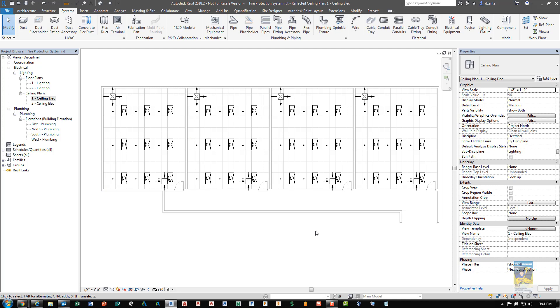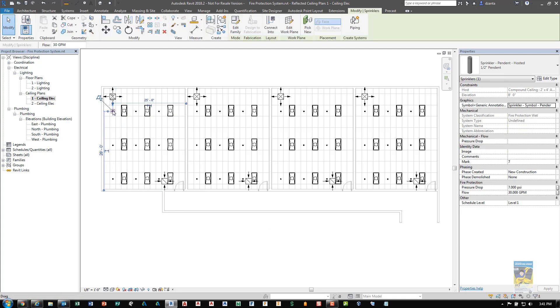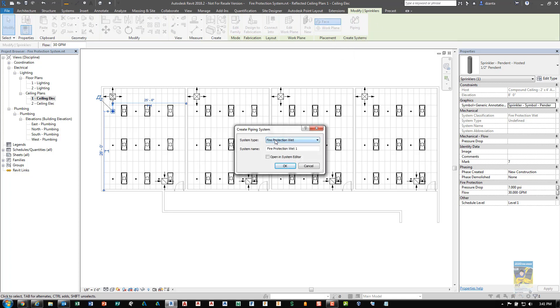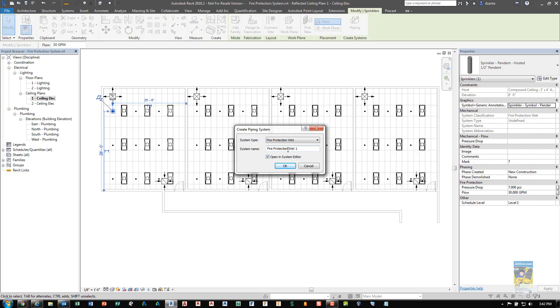The third step is to tell the software all of these sprinkler heads need to belong to a system. So select any one of the sprinkler heads that you've created. In the contextual tab of the ribbon, you'll see modify sprinklers. And in here you have a create systems panel, choose piping, and you'll get a window called create piping system. In here you can pick the type that you want to work with. This will be dependent upon what type of sprinkler head that you are placing and using. So in this example, we're going to use a fire protection wet. You can also choose to give it any name that you want. And you can also place a check mark to open it in the system browser and editor directly. So I'll click OK.